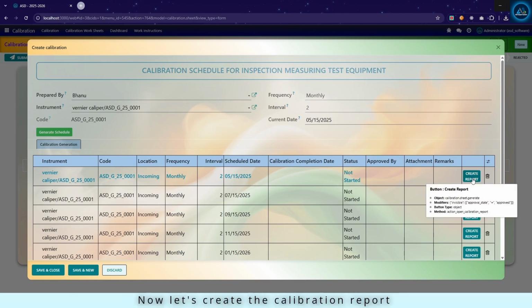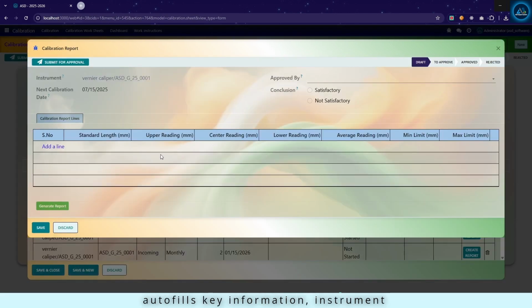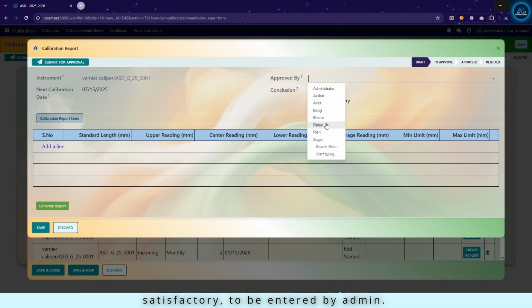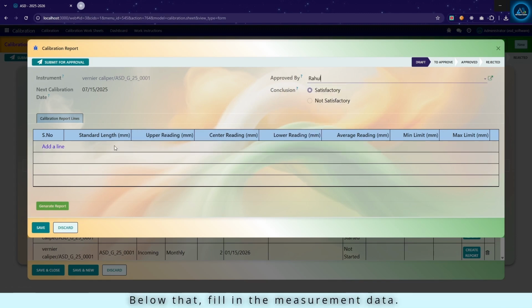Now let's create the calibration report for the scheduled date. The system autofills key information: instrument name, next calibration date, and conclusion - satisfactory or not satisfactory - to be entered by admin. Below that, fill in the measurement data. We can also attach supplier reports if calibrated from outside, maintaining a history of data.